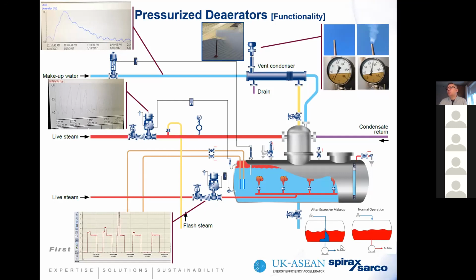And you can see is that when you add cold water to your deaerator, sorry, due to cold dumping, when you just have on-off control, there's a tendency for the colder water to be dragged to the boiler, even though the mass of water in the deaerator, where your temperature probe could say you're at a high temperature. Our own experiences found that where this control is employed, that although your deaerator may say it's 100 degrees, you could measure temperature at the boiler dropping as low as 55 degrees. And again, the ability of water to retain oxygen is determined by temperature. So again, if oxygen gets into the system, it can cause pitting and corrosion.